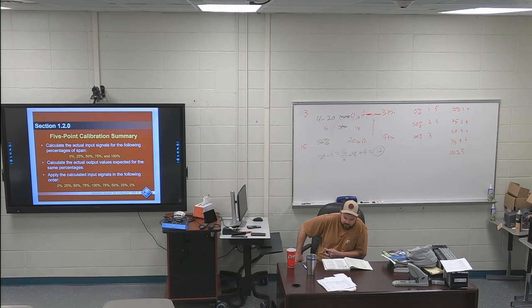So they go through the steps on doing a 5-point calibration, which you can read through if you want. I have the first half of step 9 highlighted, which is just figuring out your 50%. Calculate the expected output value. For example, the 50% point for a 4 to 20 milliamp output is 12 milliamps: 20 minus 4 times a half plus 4 equals 12, which is what we just did. Everybody good with that? So you should be able to find percent. They should be able to give you a range. You should be able to tell what the span is, and then what your different points are for a 3 and 5-point calibration.